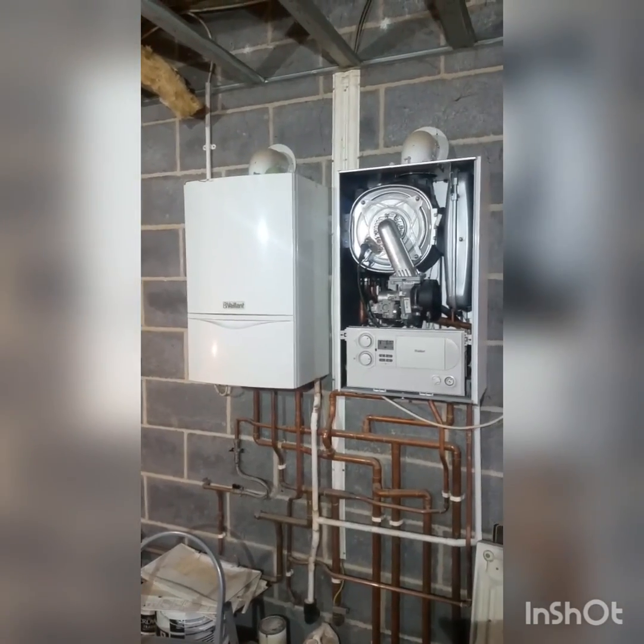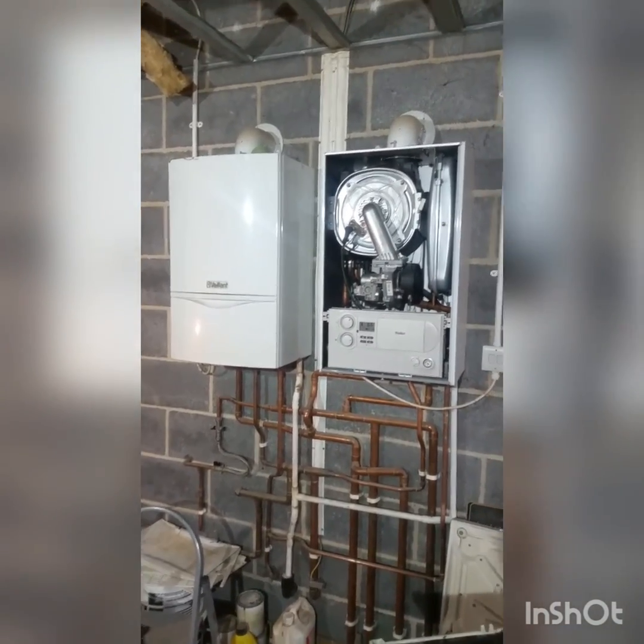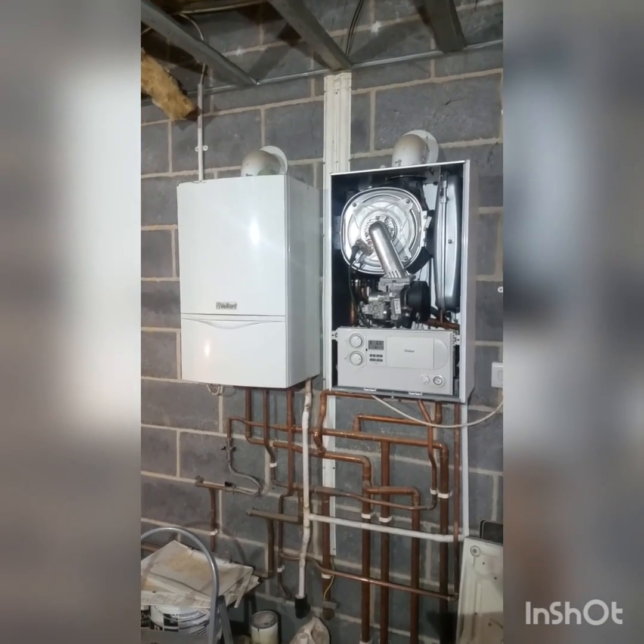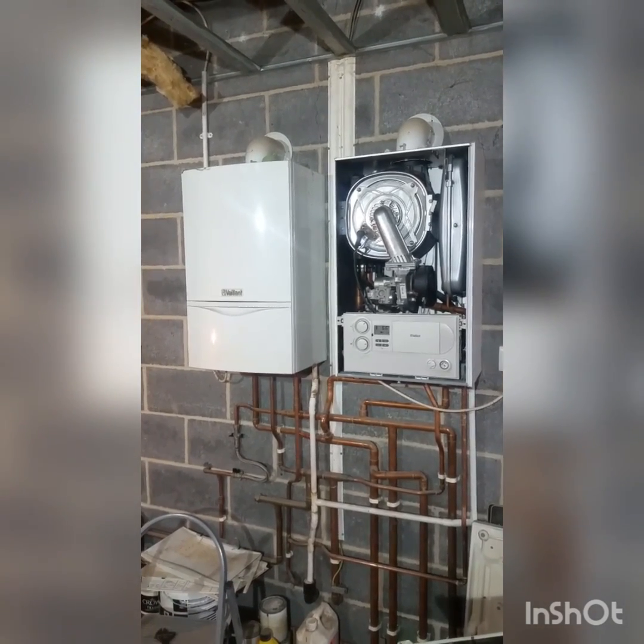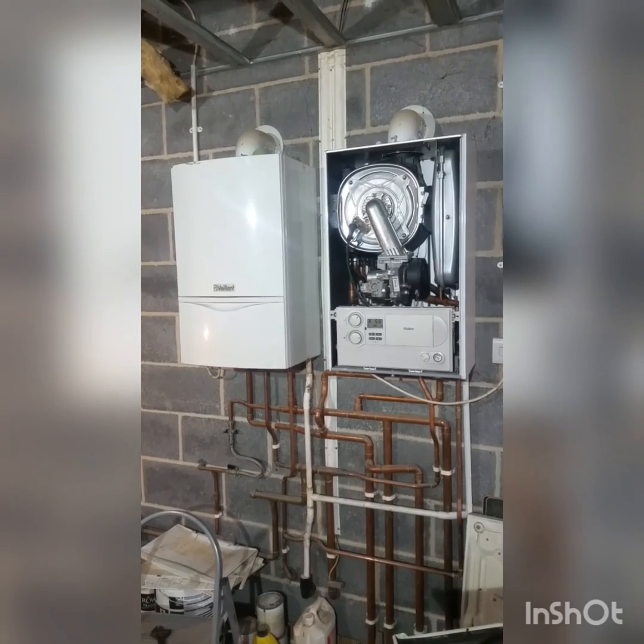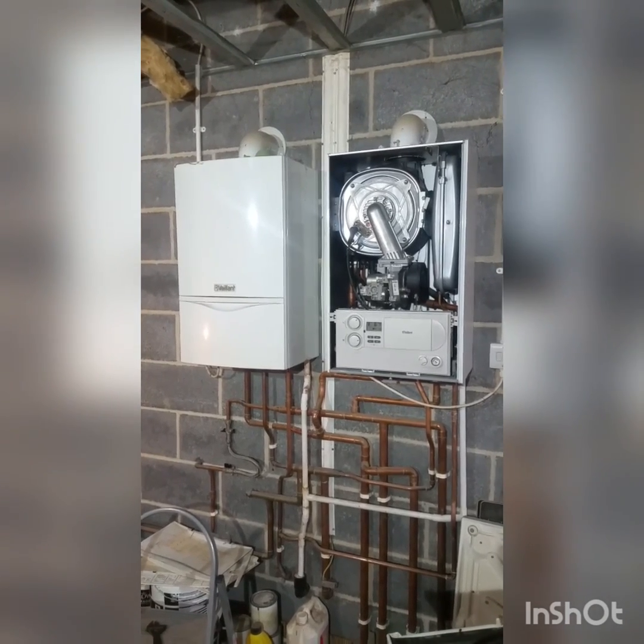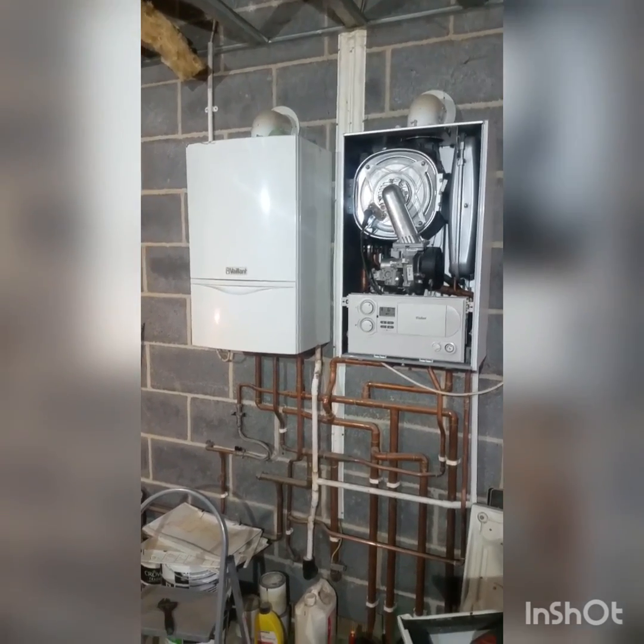The other alternative is if I give it a demand for hot water somehow. I need to speak to Vaillant about how to do that. I could perhaps set the flow temperature on the boilers within the dew point, and operate them at high temperature when they're doing the hot water.